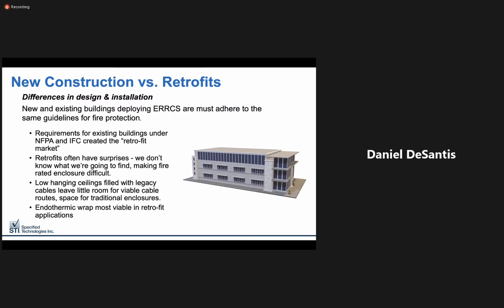EWRAP is also the lowest profile solution for circuit integrity. At just half an inch thick per layer, space becomes less of an issue and your survivability requirements are met without sacrificing finished ceiling height.